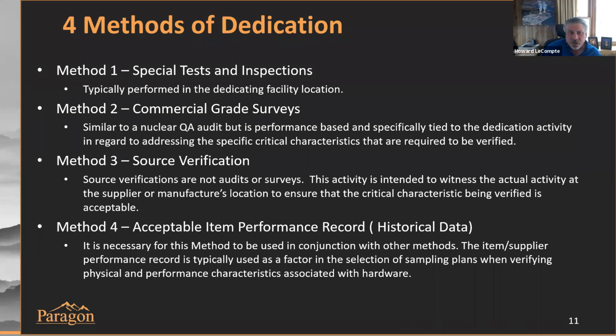One method that's not as common as the rest is method 4, historical data. We have termination logs, we've tested them thousands of times, we've never had a failure. We can take an engineering justification, use all those test results, implement method 4 along with, say, method 1 for special tests and inspections, and help reduce our sample size. That can be a cost savings for ourselves and our clients.